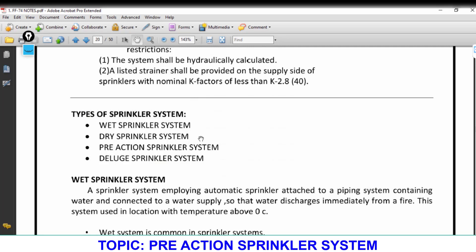In both wet and dry sprinkler systems, whenever a sprinkler breaks, water supply starts — immediately in wet systems, and within a maximum 60-second delay in dry systems. This triggers the alarm and causes a lot of disturbance and panic, especially if the sprinkler was damaged accidentally.